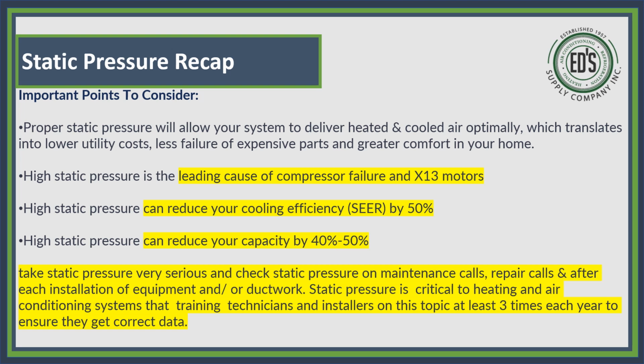You got to understand these units. A compressor is a pump. Okay. If you've ever cut one apart and taken them apart like we have here, you will see it's a magnetic motor where the windings get an electrical charge and cause an electrical field that causes a magnetic rotation on that motor. So as long as it's got power, that motor's turning, which means that compressor's pumping. All that compressor knows to do is pump. What happens is if you don't alleviate the heat that is caused from that, which is the heat removal of the house, all right, that pressure has to go somewhere. So if a fan is slowing down, you're going to cause overheating of the compressor, and it's going to go off on internal overload.